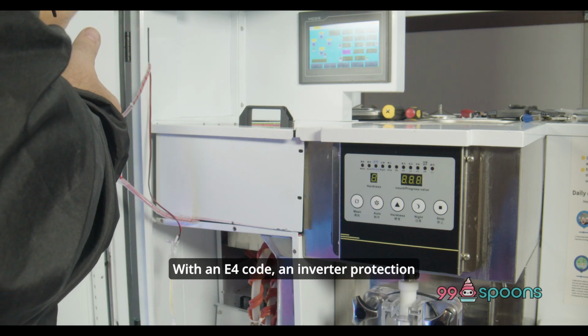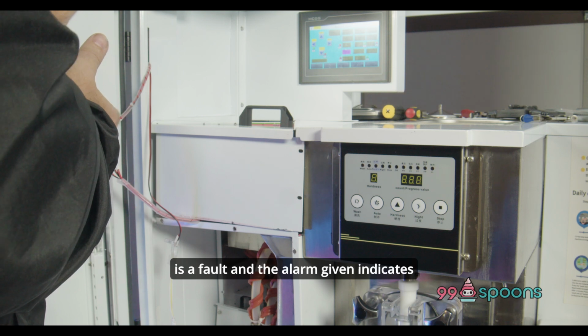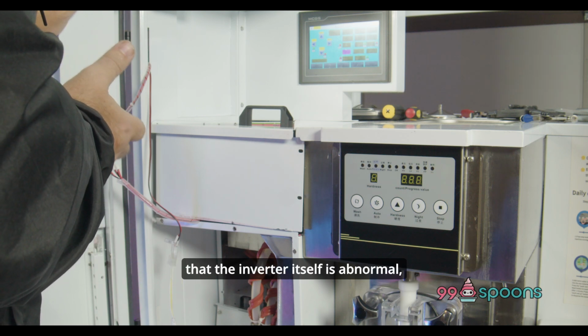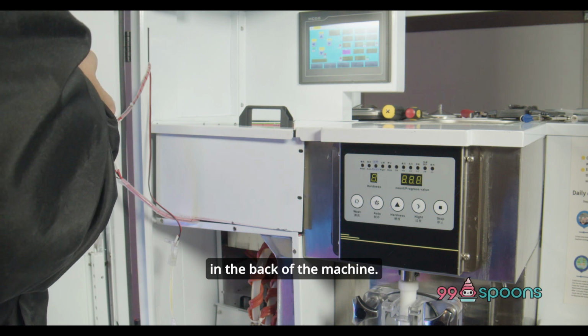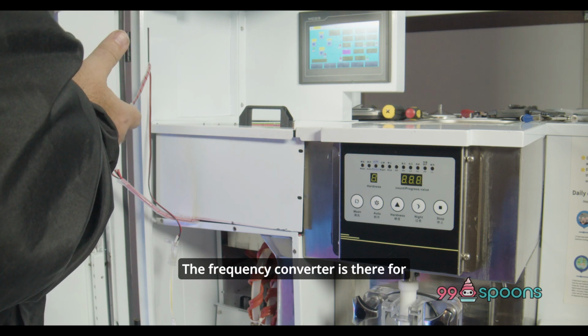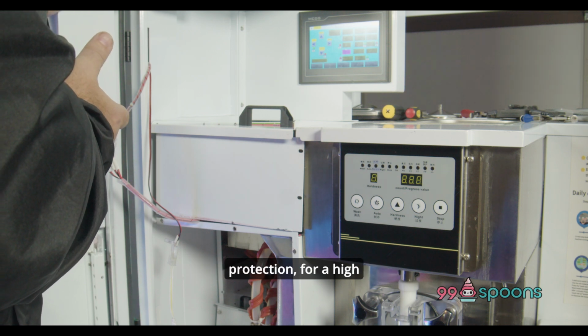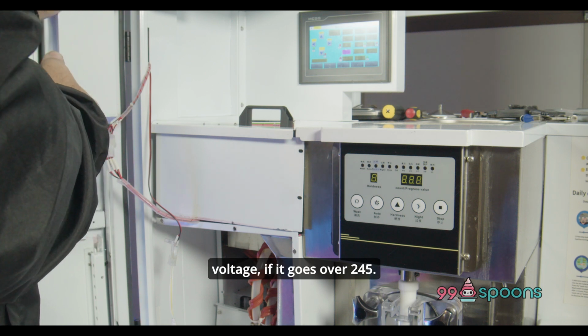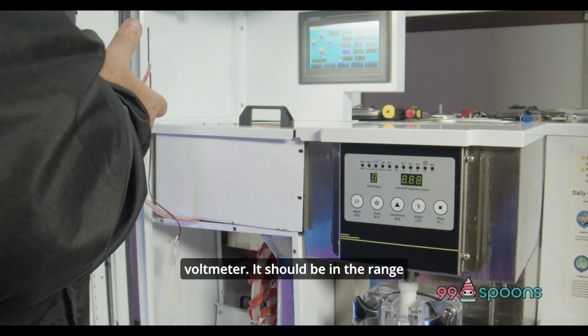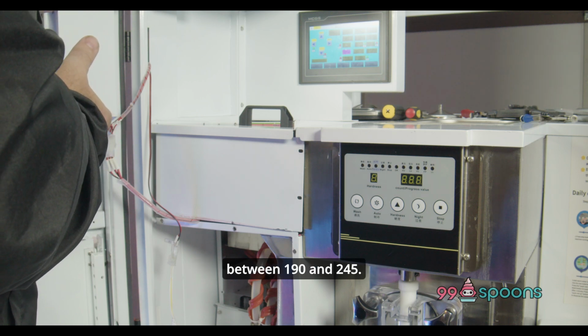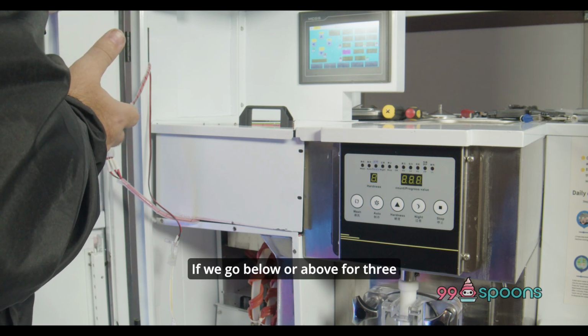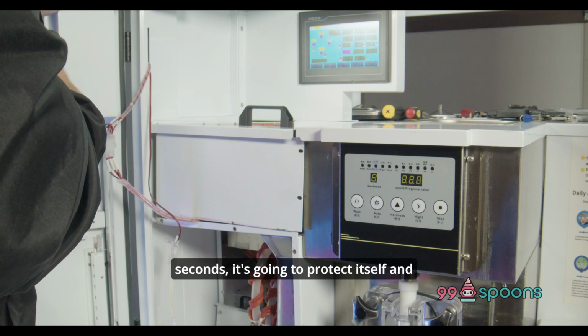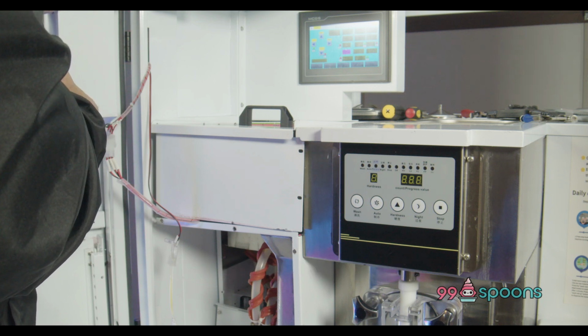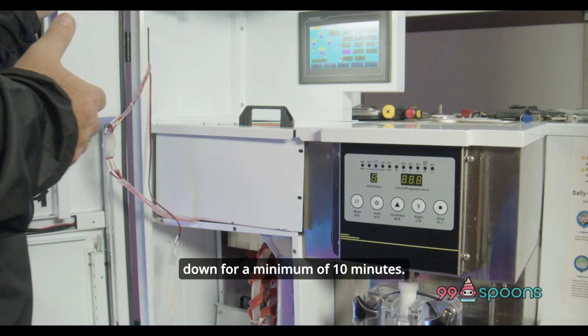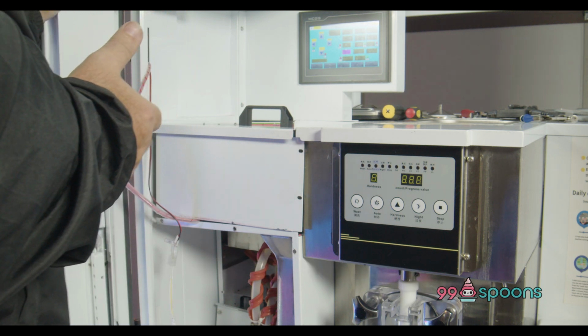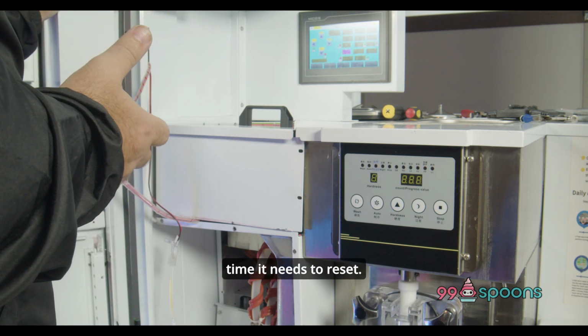With an E4 code, an inverter protection fault, the alarm indicates that the inverter itself is abnormal, which needs to be checked in the back of the machine. The frequency converter is there for protection from high voltage if it goes over 245. In the back of the machine, we have a voltmeter. It should be in the range between 190 and 245. If we go below or above for 3 seconds, it's going to protect itself and shut down. To recover, you need to shut the machine down for a minimum of 10 minutes. Don't shortcut it, because that's the time it needs to reset.